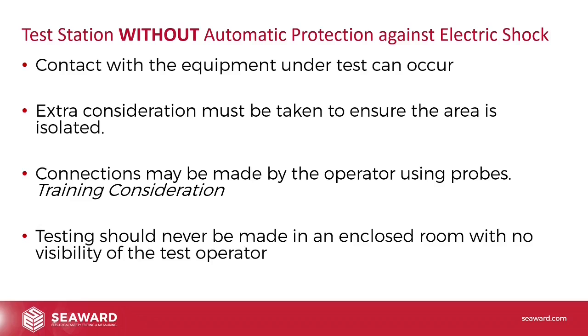But we're going to focus first on a test station without automatic protection against electric shock. Without automatic protection basically means that during a test, the operator could come in contact with the equipment that they're testing. Extra consideration must be taken to ensure that the area is isolated. Connections might be made by the operator using probes, so they might be using a probe in one hand. It's important to train the operator to know what the dangers are, because if they held the equipment with their left hand and used the probe with their right hand, there's a danger of a shock there. So there's a training consideration to be made if there's not automatic protection.